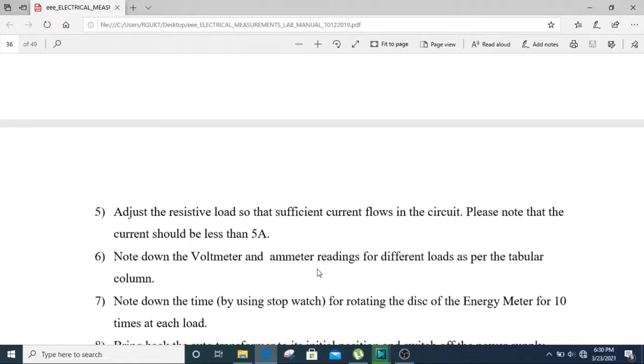Likewise, for different loads you note down all the voltmeter readings and ammeter readings, and you also note down the time taken to complete 10 revolutions using a stopwatch. Note down the time by using the stopwatch for the disc of the energy meter to rotate 10 times at each load.